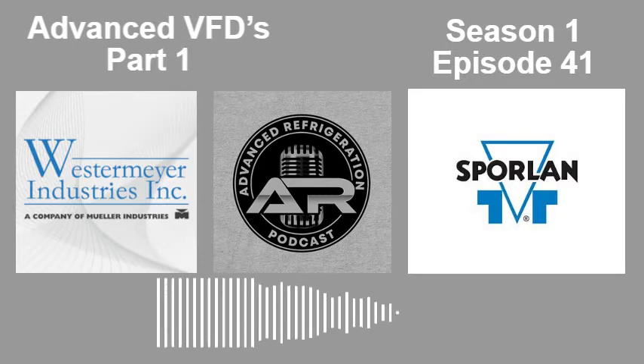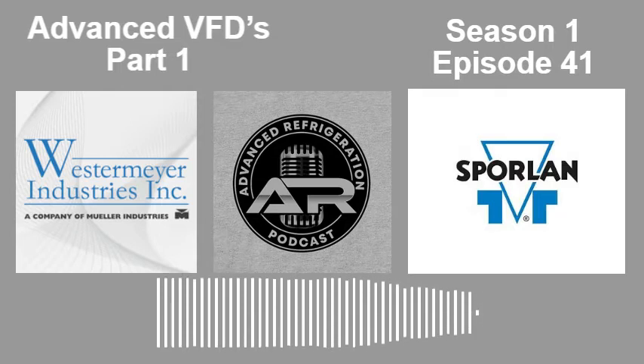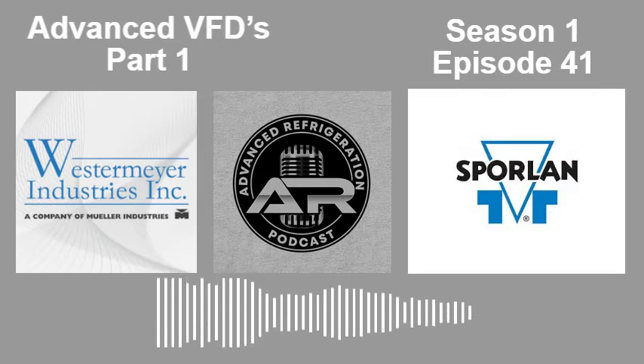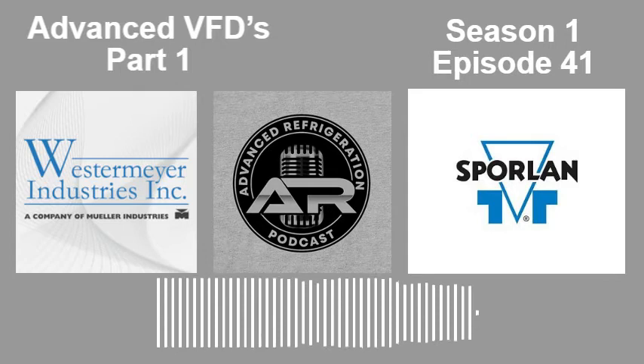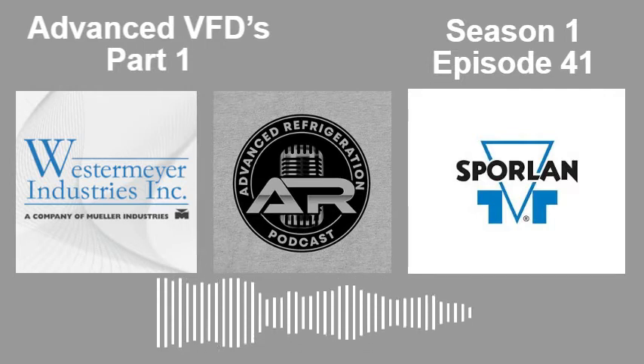Yeah, Kev, I had an instance where someone ordered a drop. I had specifically called Motion. I called Matt and got a quote from Motion. Basically gave them the part number of everything that needed to be happening, and then for some odd reason, someone else went to go install the drive. And I called Matt. I was like, man, I'm pretty sure, I don't know where we got it from, but the program's not in there. And basically that's what ended up having to happen. We had to actually send the drive out to Motion to get programmed because they goofed.